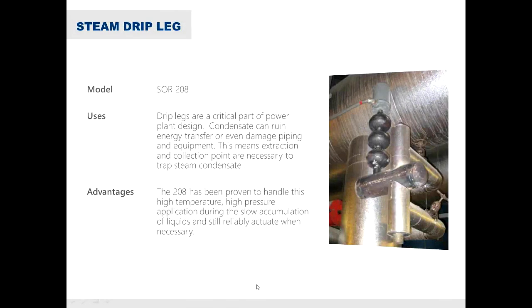Steam drip legs are all over power plants. To increase efficiency and protect equipment, they need to make sure condensate does not get into the turbines. They'll have steam condensate drip legs that catch condensate and dump it out depending on where the level is, controlling that level. These are very high-temperature, high-pressure applications, and we have custom capabilities to achieve those extreme high temperatures.